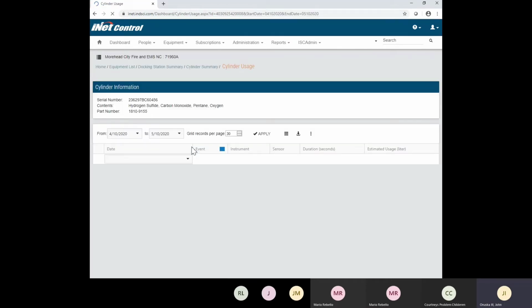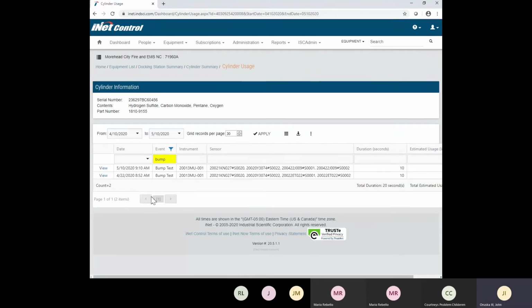Now, the reason for that is it sits there and says, okay, see, it did a bump test and a bump test. So it's saying, all right, it ran for a duration of 10 seconds. The pump runs at a half of a liter per minute. So it just does that whole math to figure out, okay, this is how much of that has actually been used. Okay. And as you can see right here, it has bump in there.